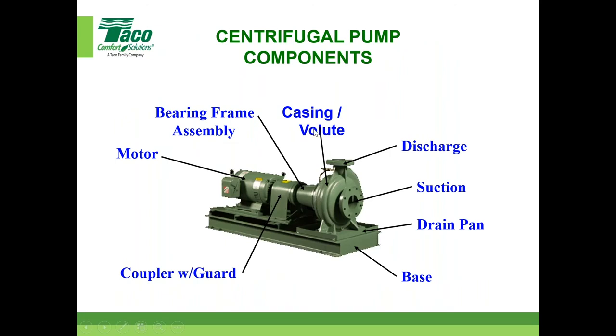That's pretty much it. Centrifugal pump components, pretty much straightforward. This is a base mounted pump, right? Well, how can you tell? Well, there's the base. The Taco base is actually four pieces of channel welded together. Obviously you can't see them all, you can kind of see it. It is enclosed all the way, but there's a cavity in here, and there's cross supports. You can kind of see these cross supports here, and it depends on the size of the pump. There could be more, could be less. And then we do have a drain. There's a solid plate underneath here, and then the drain pan sits on top, so that the wet end does rest on a solid plate. So that's our base. So that's kind of our design.